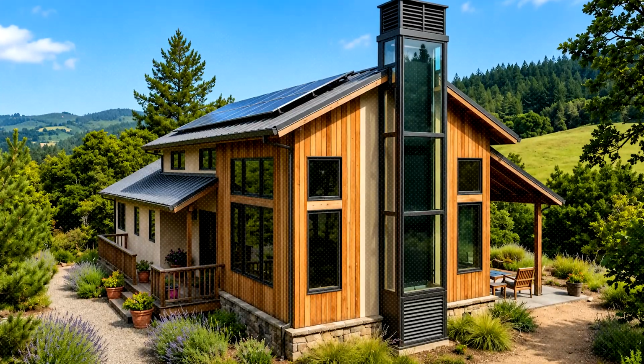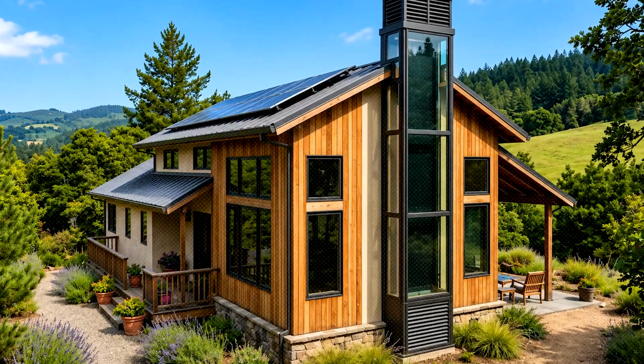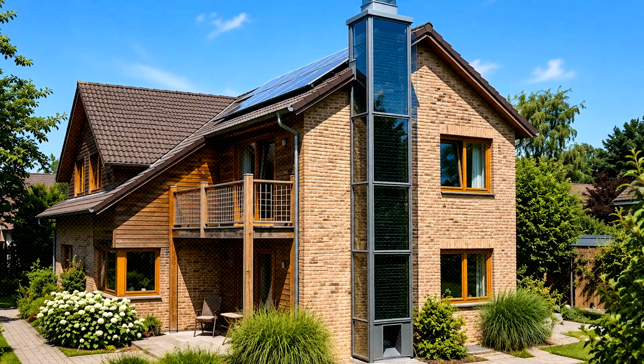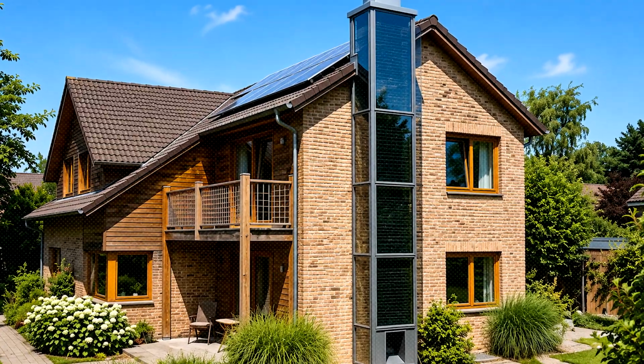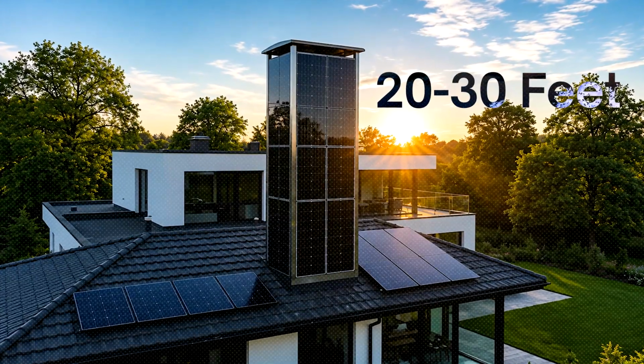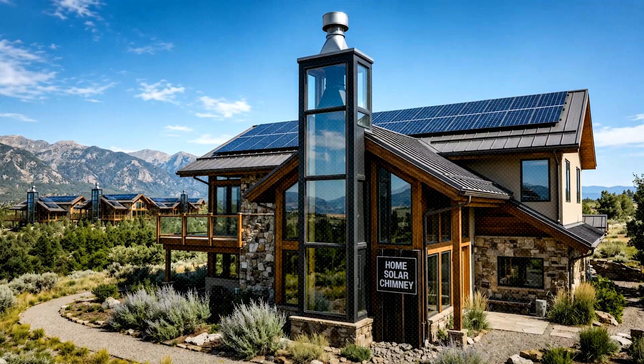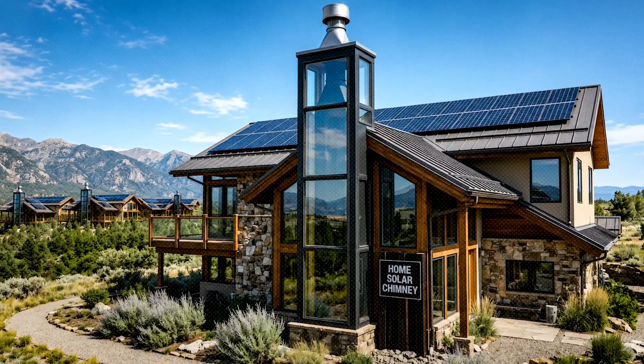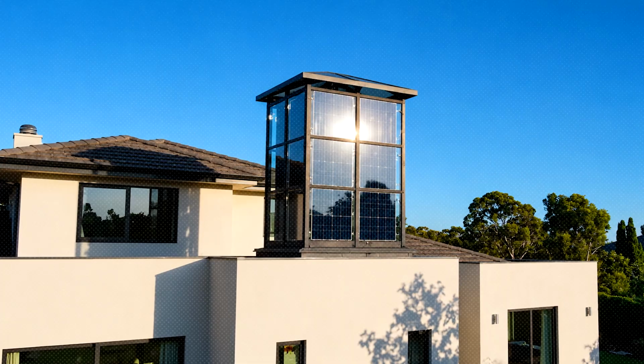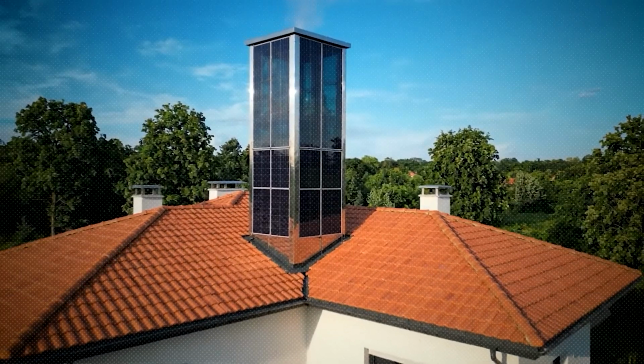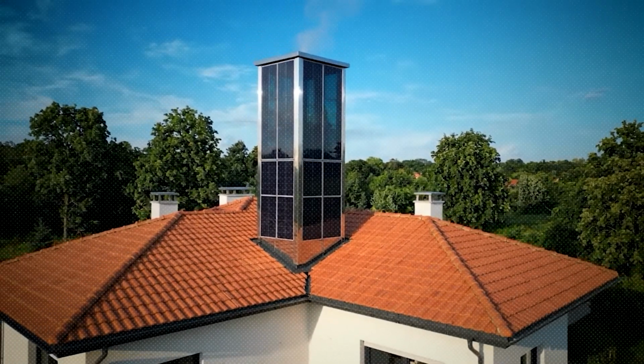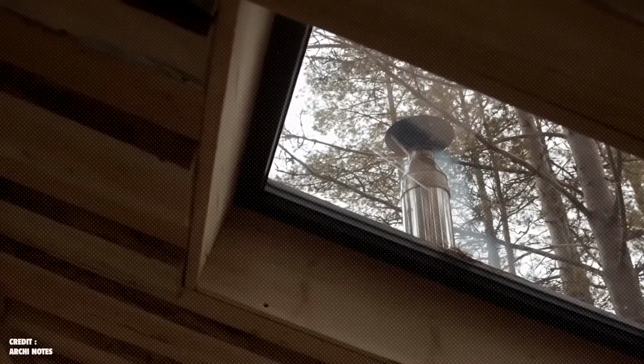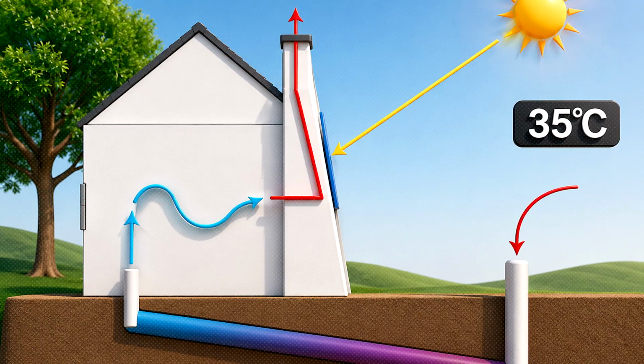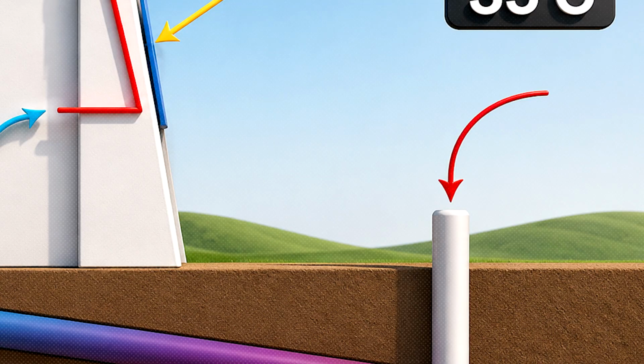For new construction, you have the opportunity to design the entire building as an integrated atmospheric engine. That means incorporating vertical shafts 20 to 33 feet in height into the south-facing thermal mass of the structure, lined with spectrally selective absorber plates and shielded by low-iron, high-transmittance glazing. Position your air intake at the lowest, most shaded point of the building. The chimney creates a continuous pressure gradient that draws geothermally tempered air in at floor level and expels hot, buoyant air through roof-level exhaust vents, 0 watts, 8 to 12 air changes per hour.